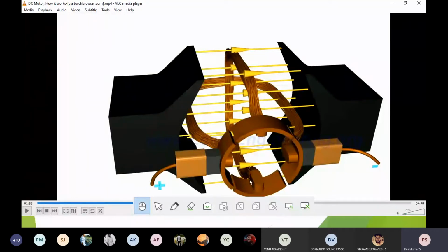That is a very big disadvantage of the DC machine. Because of these carbon brushes, I have to have a commutator arrangement. This commutator arrangement needs some cleaning. Otherwise, what will happen? Sometimes a short circuit may occur. And I have to replace the carbon brushes also. This is a carbon brush which is available in the market based on the ampere rating and so on. This has to be replaced. This is a very big disadvantage of any DC motor. Okay, we continue.